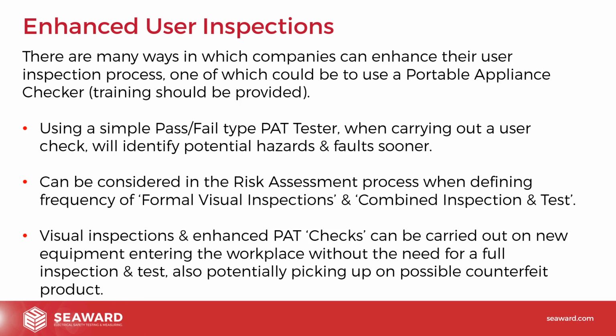Enhanced user inspections. This is what we would probably call somebody operating under level 1 competency. Sorry, he's just using a simple go, no-go tester. There is an option to say, could we carry out what we call enhanced user inspections? So could we do a user inspection, a user check, a visual inspection, but add a very basic test with a go, no-go style tester, a pass-fail style tester, to check the things that they can't physically see. There are many ways in which companies can enhance their user inspection process, one of which could be the use of a portable appliance checker. And obviously training should be provided on the use of the equipment.